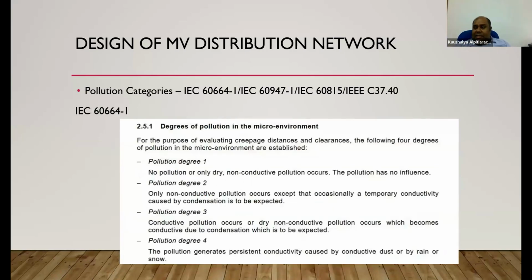Pollution categories. This is discussed in several standards. A few IEC standards: 60664-1 insulation coordination, 60947-1, 60815, and IEEE C37.40. In insulation coordination standard 60664-1, it describes the pollution category in 4 particular degrees. Pollution degree 1: no pollution or only dry non-conductive pollution occurs. The pollution has no influence on the creepage.